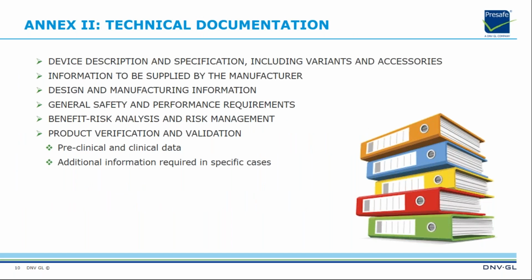Annex 2 is about technical documentation, and for the technical file and technical design dossier system, you have to provide details about products, including documents to demonstrate the safety and performance of your product, in addition to the essential requirements. In essential requirements, you have to refer to this technical documentation to demonstrate the safety and performance of the medical device.